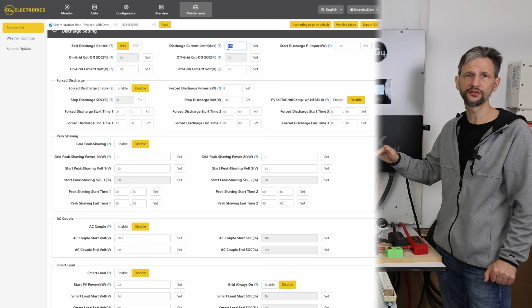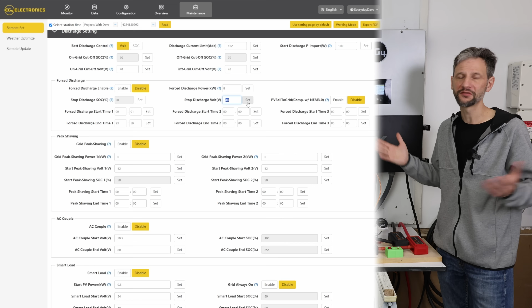And now for the end of discharge voltage. The BMS limit is 10 volts, and that's when it'll shut down. 4 times 10 is 40 volts, but there's very little capacity below 48 volts. So I can set the pack to a minimum of 48 volts to reduce stress on the battery and still use 95% of the battery capacity. And that's all the settings we need to allow us to run with this inverter.